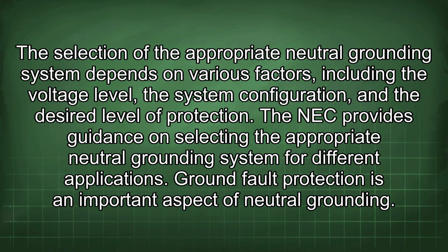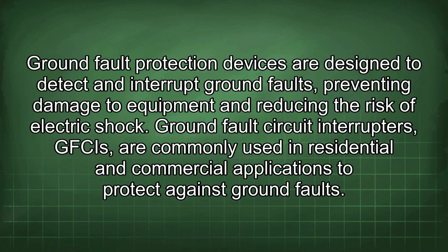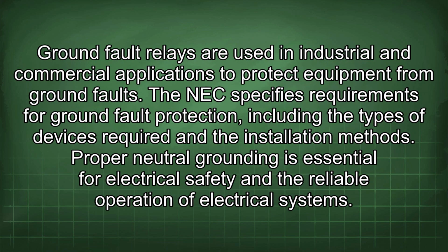The NEC provides guidance on selecting the appropriate neutral grounding system for different applications. Ground fault protection is an important aspect of neutral grounding. Ground fault protection devices are designed to detect and interrupt ground faults, preventing damage to equipment and reducing the risk of electric shock. Ground fault circuit interrupters, GFCIs, are commonly used in residential and commercial applications to protect against ground faults. Ground fault relays are used in industrial and commercial applications to protect equipment from ground faults.